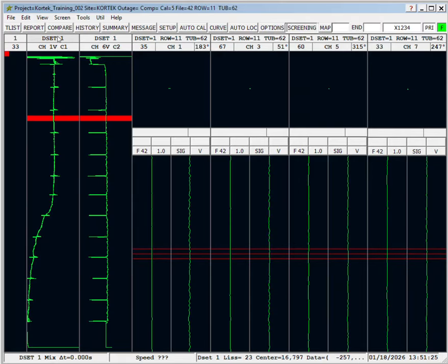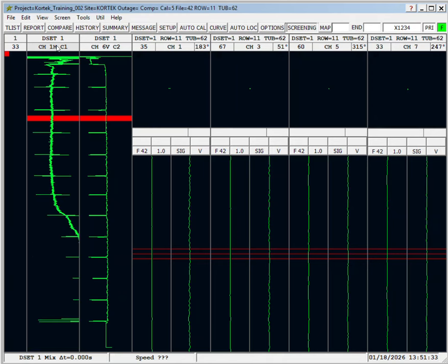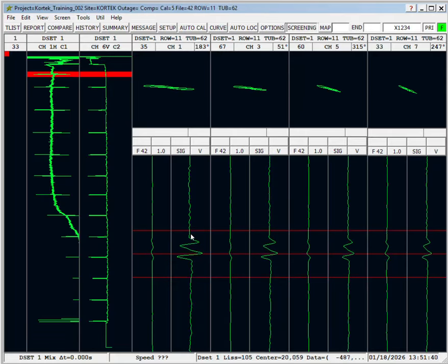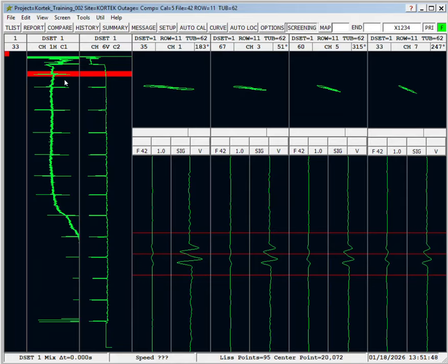Now, one thing about strip charts, remember we're watching the vertical component of these strip charts. If you do a middle click on here, you're going to change to the horizontal. And when you do that, look at how much this dent signal sticks out on the horizontal strip chart. That's because these strip charts will display either the horizontal component or the vertical component. Large deflection on the horizontal strip chart, that's because there's a large horizontal excursion in my expanded strip charts.